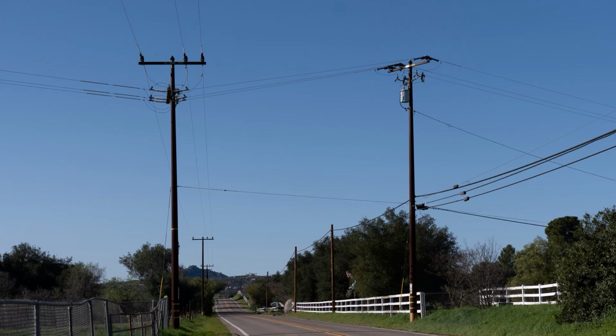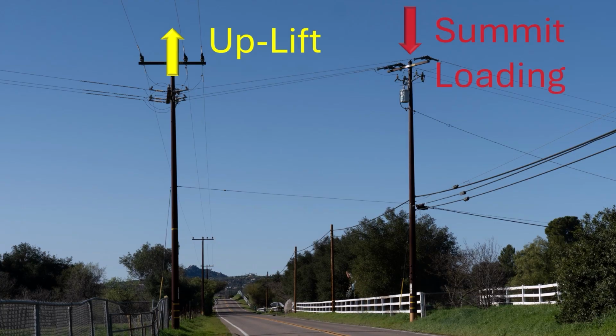You can see both of these loads happening here. The pole on the left is being subjected to some uplift caused by the much taller pole on the right, and the pole on the right is being subjected to some additional summit loading as a result.